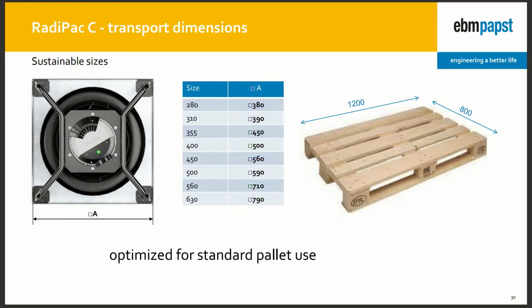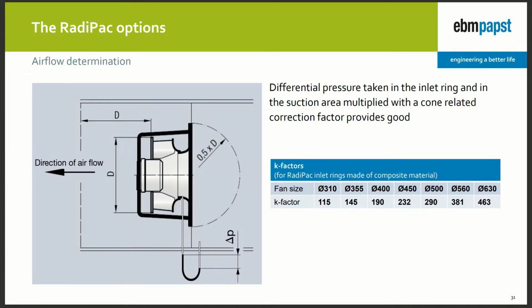And this is a small note on airflow determination. In all backward curved centrifugal fans, you can easily measure by a pressure tap the differential pressure between the air intake and the inlet cone, and you can calculate the airflow with a simple formula. This is quite accurate and, with some control devices, helps to provide the right amount of air.